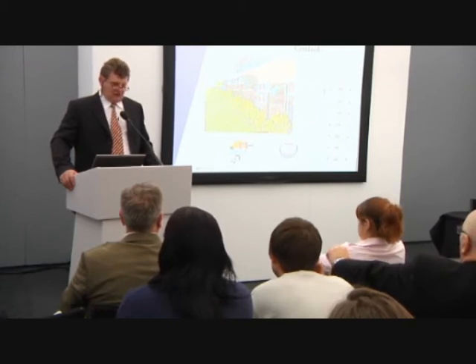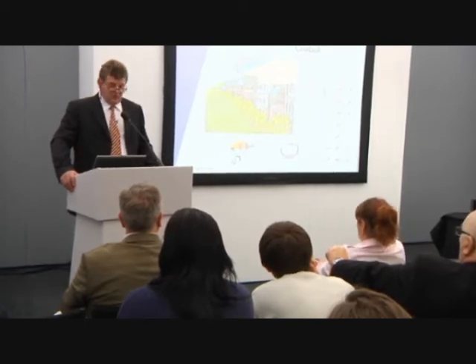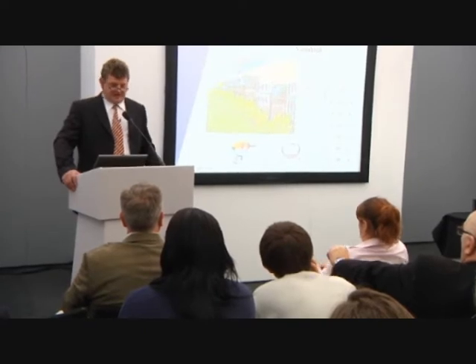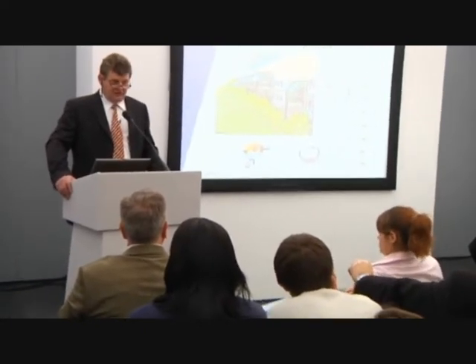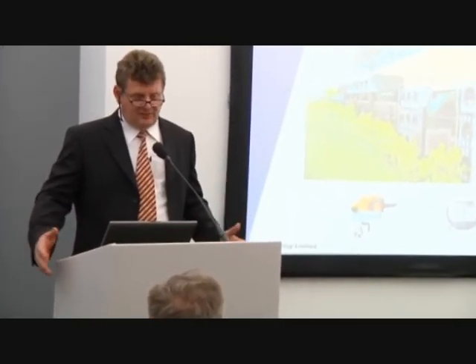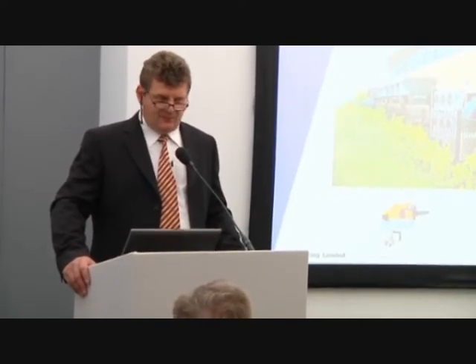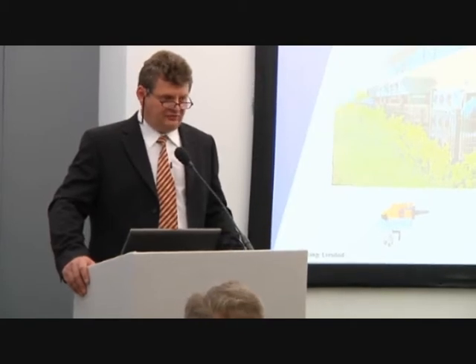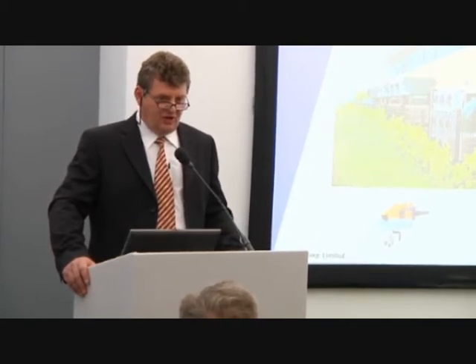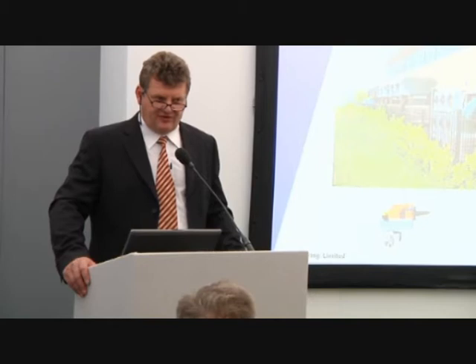How we control a computer room is based on two things: temperature and pressure. We monitor the pressure of the raised floor — the underside of the raised floor. Because we know if we're achieving 20 Pascal of pressure in that underfloor, we're getting the right flow. A key part of commissioning is to understand how your raised floors are working and what total flow rate the server room requires. Give it the right amount.